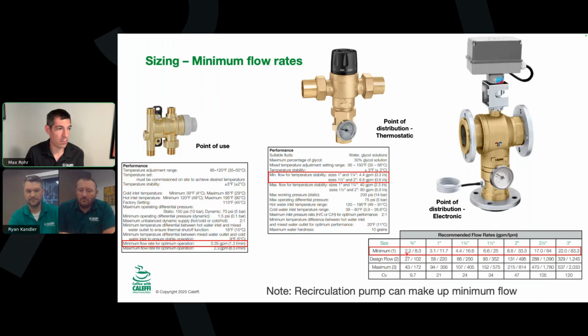But as soon as you meet that minimum, which is a lot lower with the digitals than with the thermostatic, so 4.4 versus 3.1 for 1-inch valves there. As long as you exceed that, the recirc pump should take you most of the way there, even if it slows down like an ECM pump should. That's when you're going to see that stabilize.